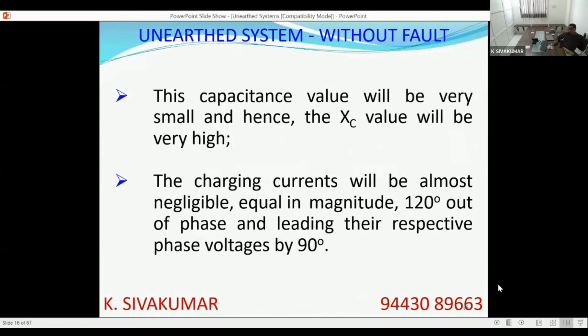This capacitance value will be very small and the XC value will be very large, because the dielectric distance is very high, so the capacitance value is small. Since XC is 1 by 2πfC, the capacitive reactance will be very high. Since the capacitive reactance is very high, the currents are very small, negligible.